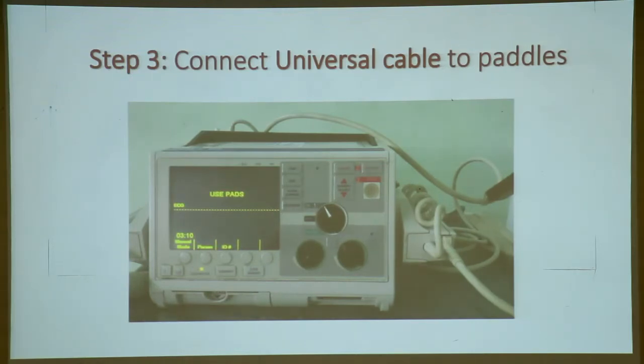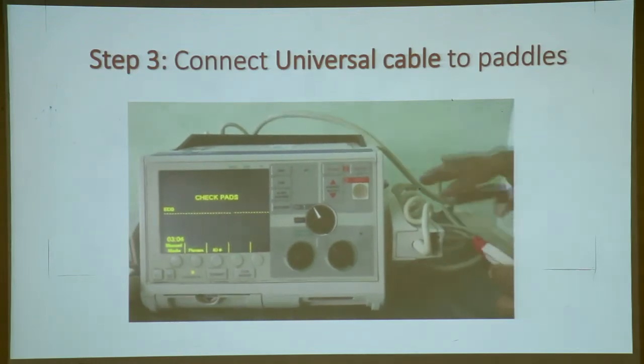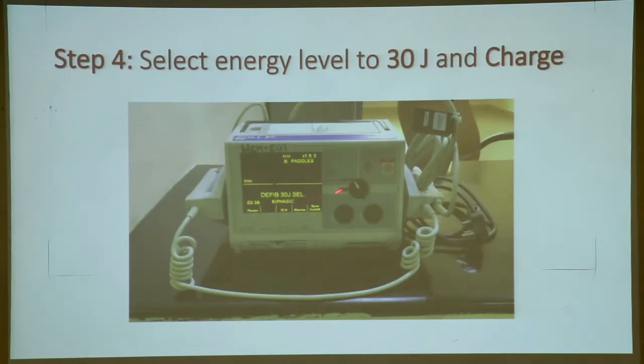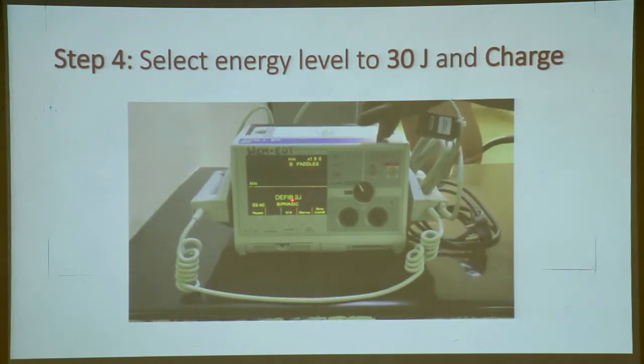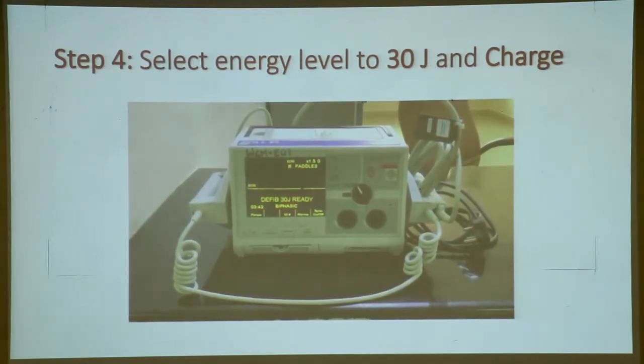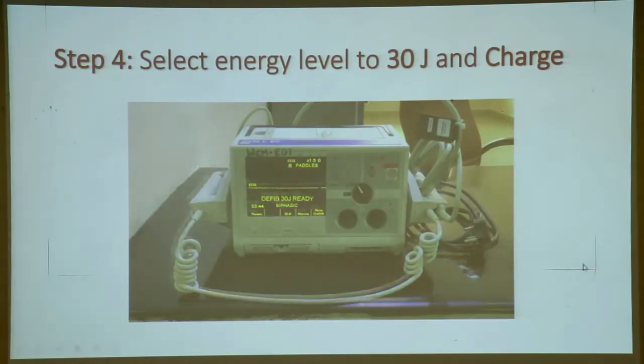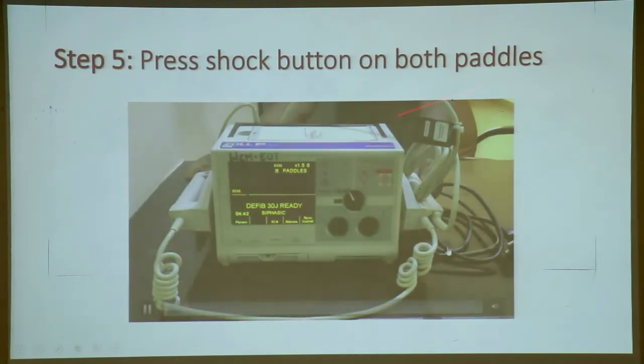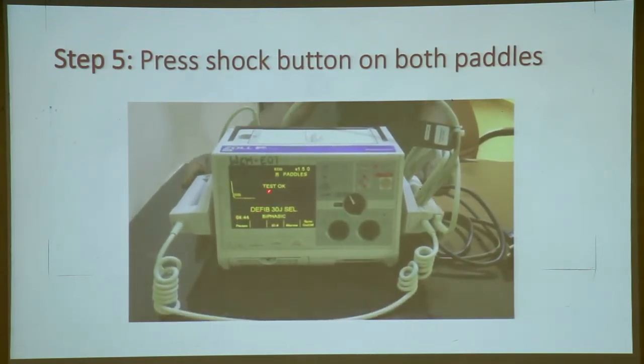Okay, it's very easy to say defibrillate, but this is what you need to do every day to know how to give the shock. So once you have connected this universal cable to the paddles, which is generally not kept connected, right? Then select the energy to 30. Charge it up, let it go to 30, and it will give you a continuous audio-visual beep that it is ready. Next, you select both the buttons and then discharge. It says test is okay.